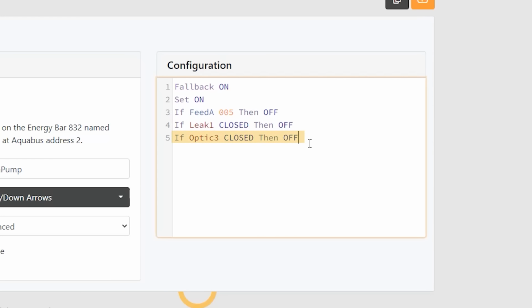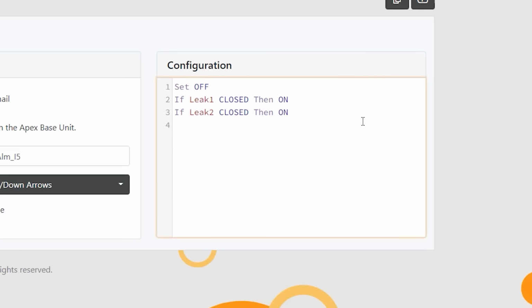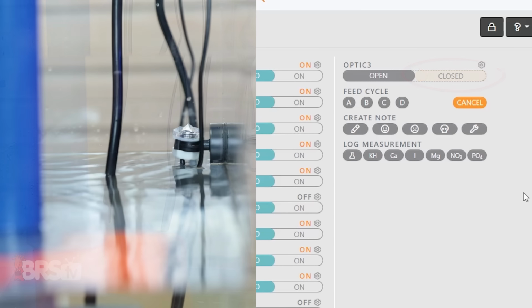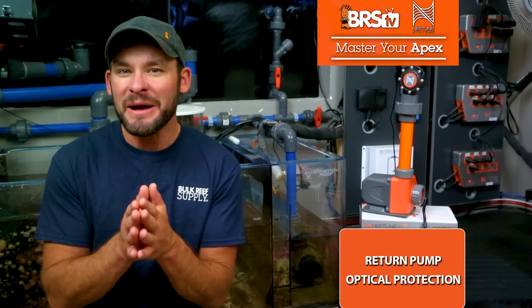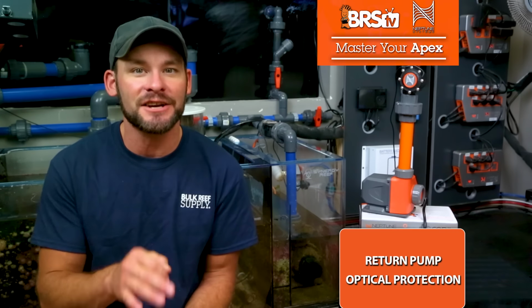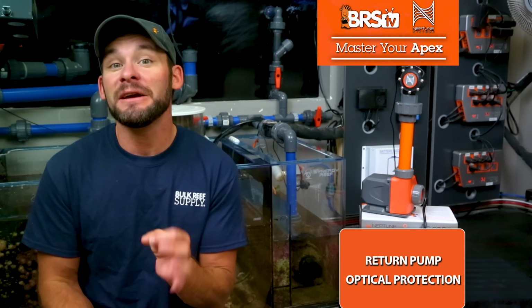says, if Optic 3 closed, then off, and a line into your email outlet that reads, if Optic 3 closed, then on. The key here is to remember that the optical sensor is closed when underwater and open when dry, and it's best practice to test your alarms and actions after you're done to make sure that they function the way you intended.